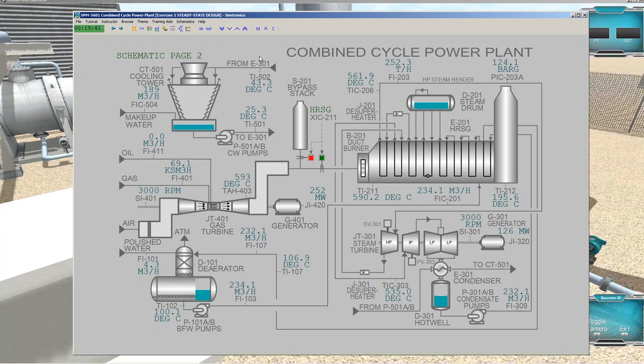And that can also be an alternative operation just in case you have to take the steam turbine generator out of service and you still want to run the heat recovery steam generator. Take all that steam and just bypass it around the steam turbine and then condense it and then exhaust, of course, all that heat to cooling water. Okay, and that's it in a nutshell.